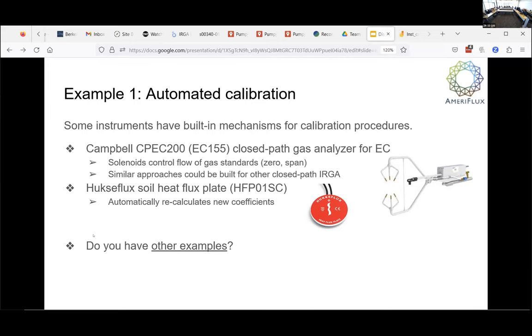Well, somebody said this too, that a long continuous record of data that has a problem with it, but it's a fixable problem, is much easier to deal with than a record of data that's got a bunch of different pieces that all have different problems that you have to treat individually. And so even if your calibration is off by an offset or a gain factor, it's all the same for the entire year. That's really easy to fix. But if I have every month a new calibration that has a new problem, that's really hard to fix. And I'm probably not going to get it right anyway. I would rather have the data that's consistently wrong rather than randomly wrong. Yeah, I mean, that's the part that's hard to correct for.